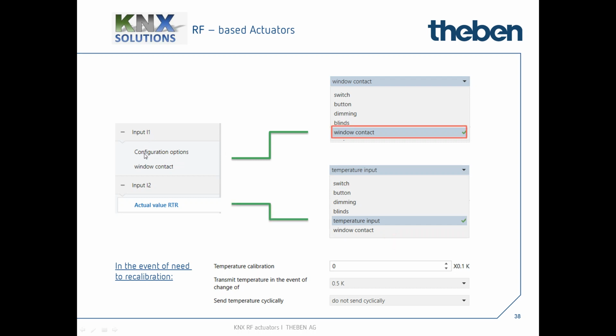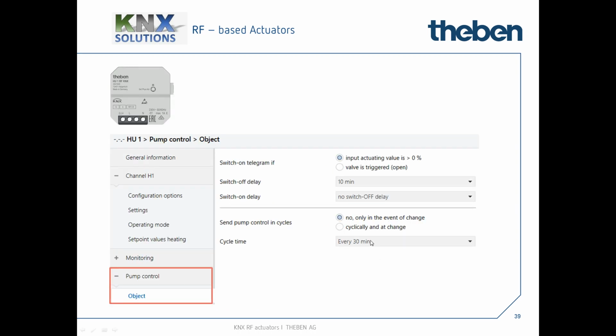Just an example: input 1 could be a window contact, so the setting could be that if the window contact is open, you lock the heating activities so that the warmth does not escape through the open window. And input 2, for instance, could be the actual value of a room temperature, so a small temperature probe. If there is any difference between the measured temperature and the real current temperature in the room, you have the option in a specific setting to do a temperature calibration and give an offset up or down, so plus or minus is possible.